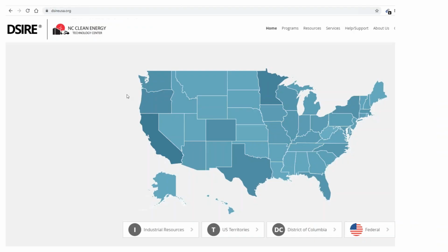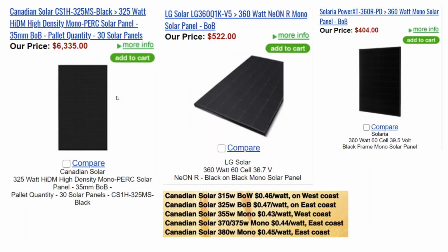If I'm buying a pallet of solar panels and I see that it's 30 panels in a pallet, I know that's 15 per circuit. I can say, okay, that's 2 branch circuits. That's really easy. And so if I'm trying to optimize my project and I have a pallet of panels that's 24 panels or 25 panels, and I get another pallet that's 30, if I have good net metering and I still have the electric bill, 30 panels divides 15 per circuit, you can have up to 16, and that's great.